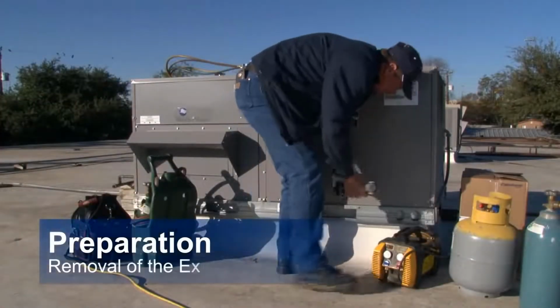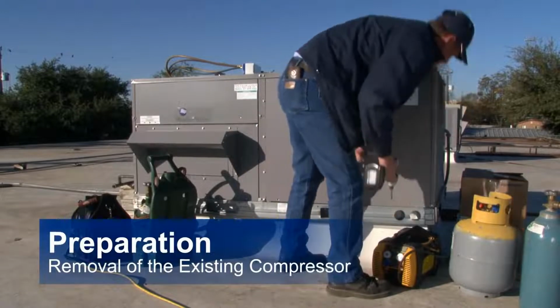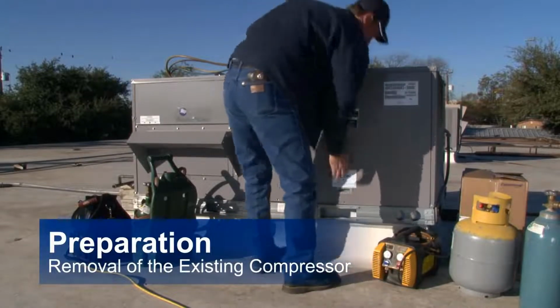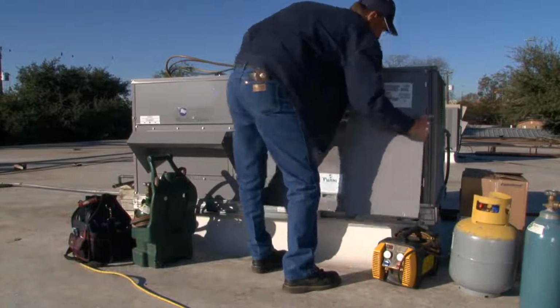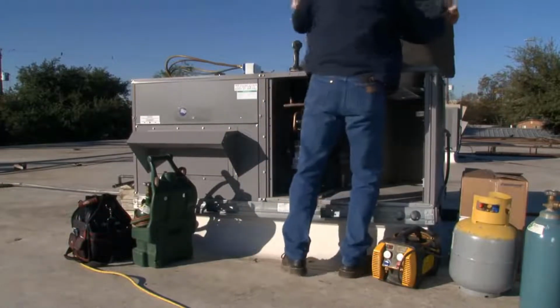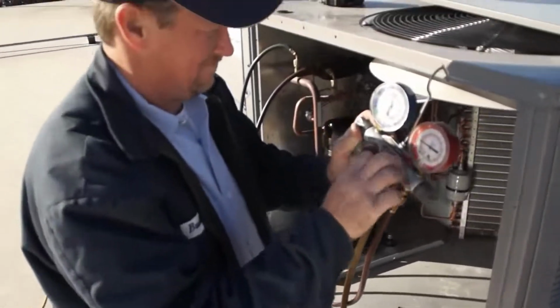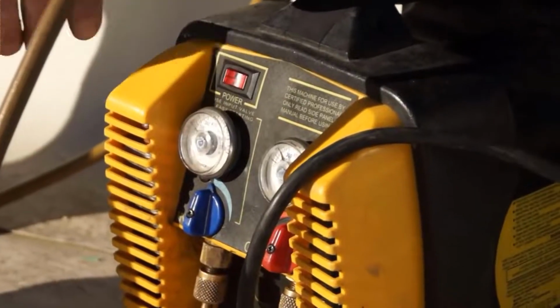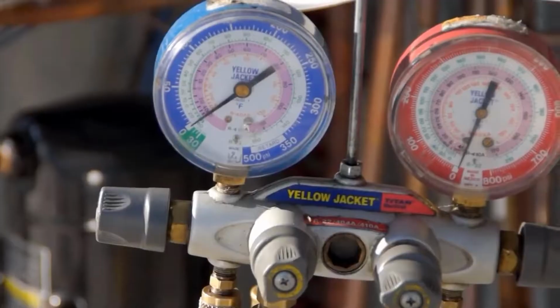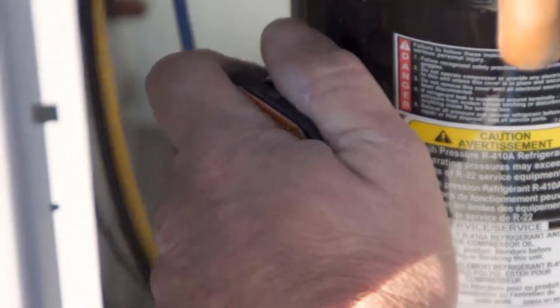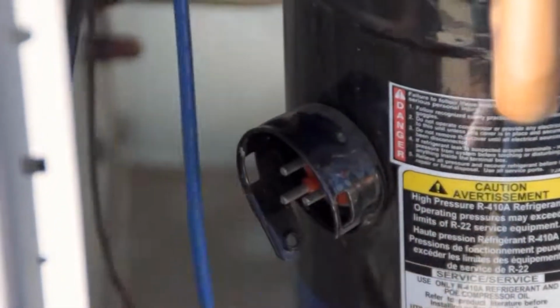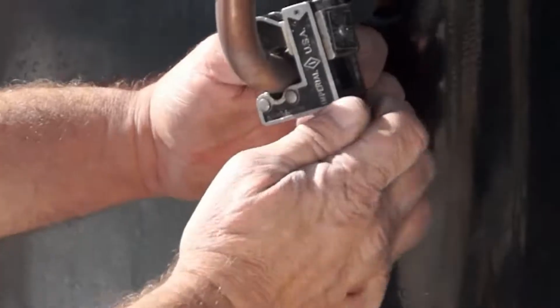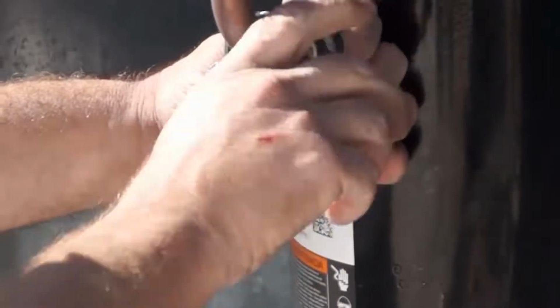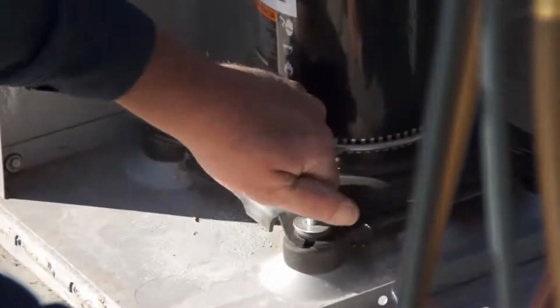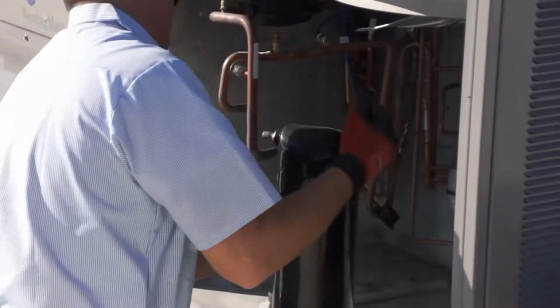To begin the installation process, the existing compressor must first be removed. Be sure to disconnect and lock out all power to the system. Remove the unit's service panels and connect gauges and recovery equipment to properly evacuate the existing system refrigerant. Once evacuation is complete, disconnect all electrical connections near the compressor, like the molded plug and pressure switches. Cut the copper connections and free the suction and discharge lines from the compressor. Undo the mounting bolts and the compressor can now be removed.